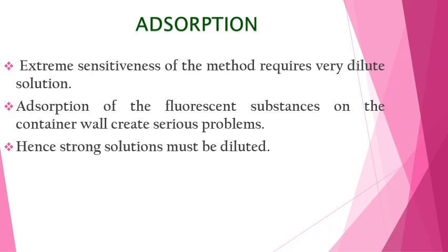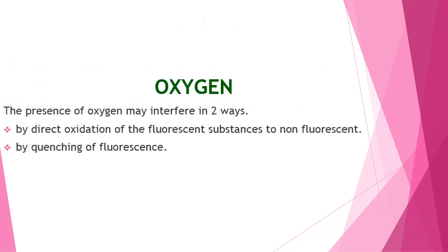Adsorption. This method is very sensitive. So the adsorption of the fluorescent substance on the container will create serious problems. So strong or concentrated solutions must be diluted. This leads to a decrease in the fluorescence. Intensity of incident light: an increase in the intensity of incident light on the sample also increases the fluorescence intensity.